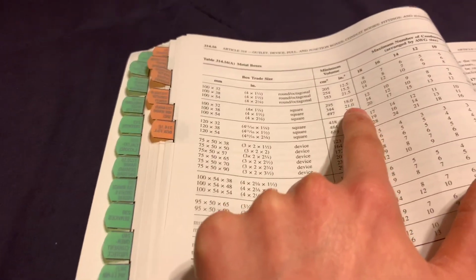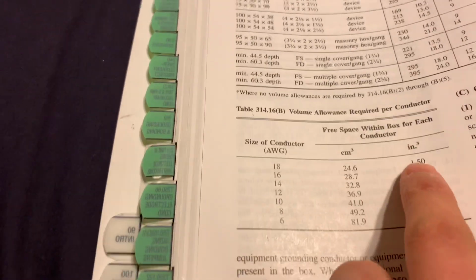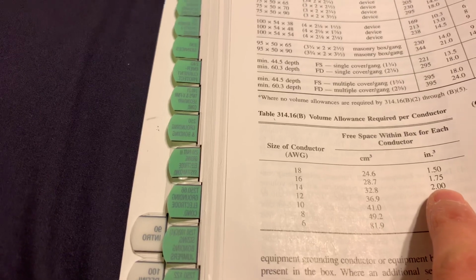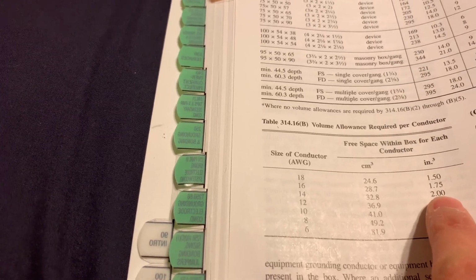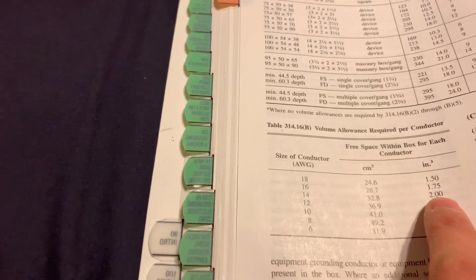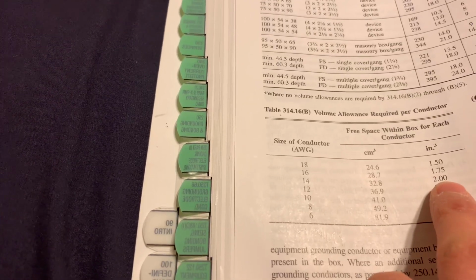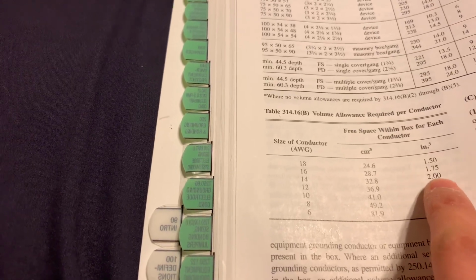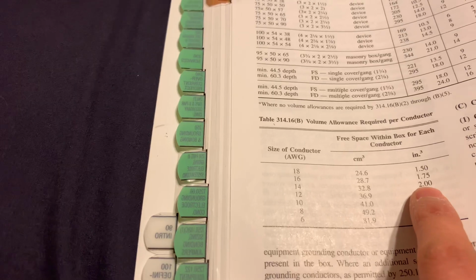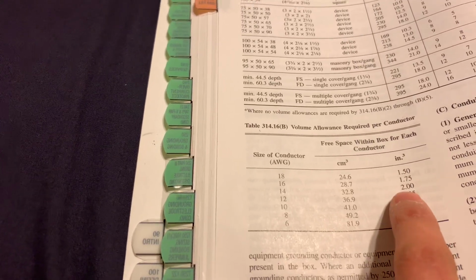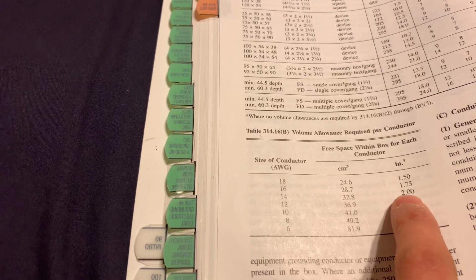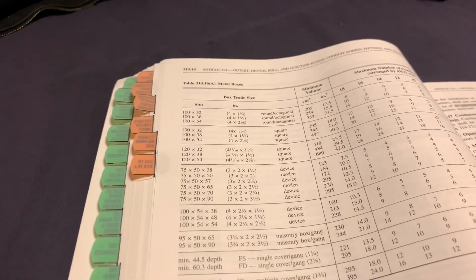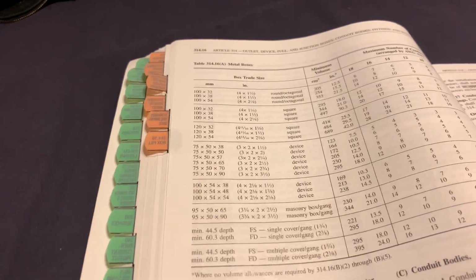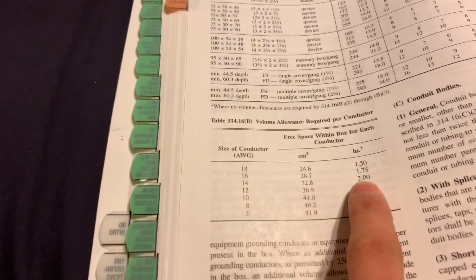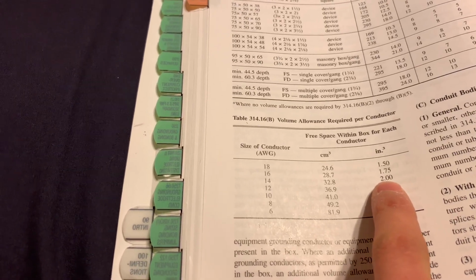So in that 21 inches in your box, what is that going to be? I have to think real quick. Each wire counts, so the hot and the neutral count, if I'm remembering this correctly, it's been a while. The hot counts for 2, neutral counts for 2, and then there's one ground. So that's 6 out of the 21 cubic inches. So you basically can have 3 wires, 3 14 wires, that's 18, right? Man, I really hate thinking on the spot, but I want to do this in one video.